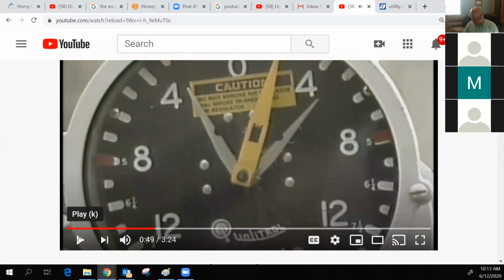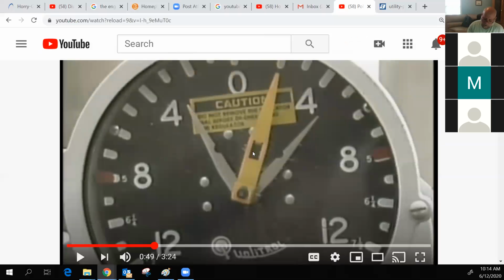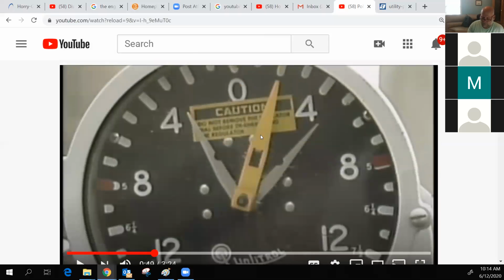Just like I think Capezzi said a minute ago, I think he's the one that mentioned the steps on it. There's actually 16 raised steps on this regulator, and there are 16 lower. If the voltage gets too low, then these arms right here, that yellow arm, it'll start moving down to the right. If it's on 2 there, then it's going to bump up to 8 if it needs to.